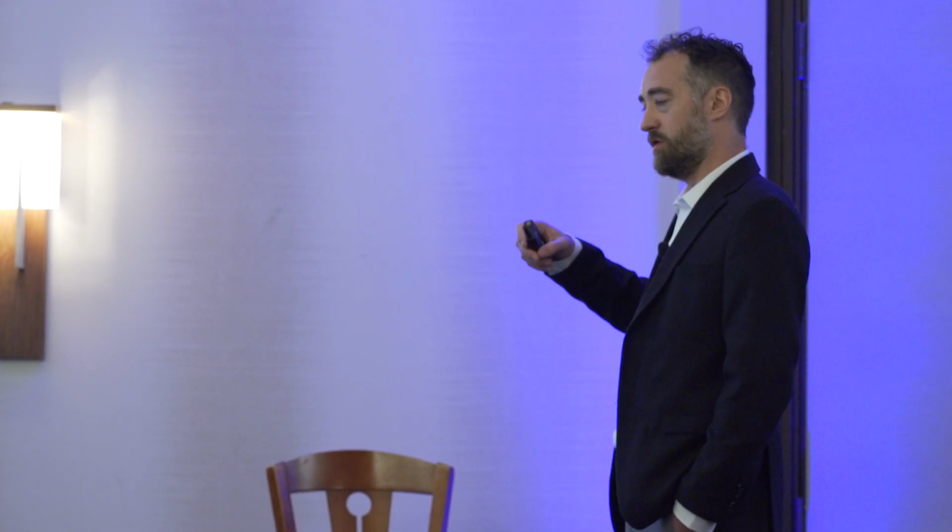An optimizer is an algorithm that uses linear programming and regression to refine complex sets of data into something simpler based on input criteria that specifies what you want to get out of the end result, right? So, for example, I'll say electrically again. We would say to the optimizer up front, maybe we've got a good rate on panels. Panels are cheap. You can use as many panels as you want, but we want you to minimize the length of the tool install cables between the tools and the panels. Or we've got a really bad rate on panels. We want you to minimize the number of panels in the facility. So you can kind of tweak it that way.